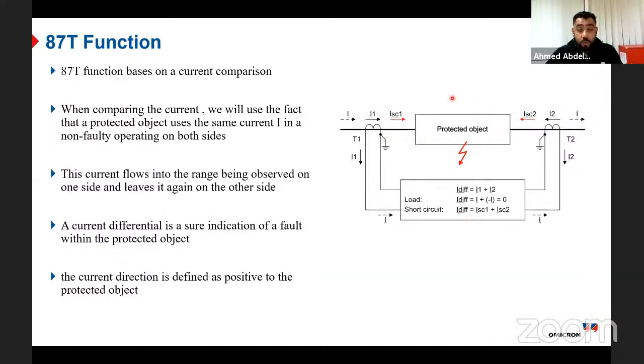The difference between the two currents, the current in and the current out, is a clear indication there is an internal fault. Let us assume I don't have I short circuit 2 because I don't have anything here on the right side. So I have I short circuit in, but it doesn't go out. Who will tell me that this current is in or out? The CT. So the definition of the protected zone is the CT. The area between the two CTs, I can call the protected zone. If a current passes the CT T1, like a monitor or a guard, but it doesn't reach CT T2, it means there is an internal fault. Here is the definition, the differentiation.